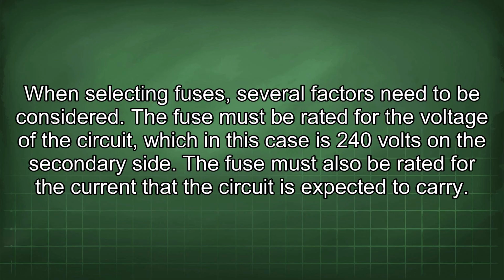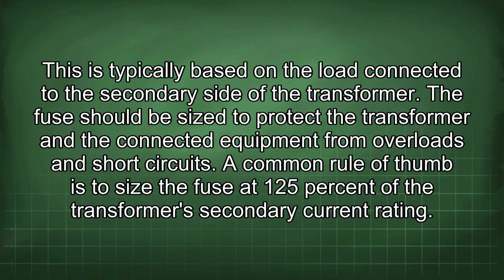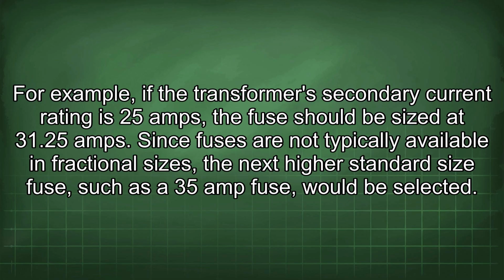When selecting fuses, several factors need to be considered. The fuse must be rated for the voltage of the circuit, which in this case is 240 volts on the secondary side. The fuse must also be rated for the current that the circuit is expected to carry. This is typically based on the load connected to the secondary side of the transformer. The fuse should be sized to protect the transformer and the connected equipment from overloads and short circuits. A common rule of thumb is to size the fuse at 125% of the transformer's secondary current rating. For example, if the transformer's secondary current rating is 25 amps, the fuse should be sized at 31.25 amps.